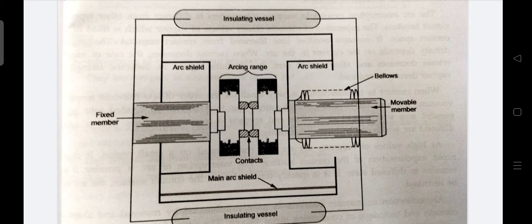For example, when contacts of a breaker are opened in vacuum, the interruption occurs at first current zero with dielectric strength between the contacts building up at a rate thousands of times higher than obtained with other circuit breakers. The principle of vacuum circuit breakers is the production of arc in a vacuum circuit breaker and its extinction can be explained as when the contacts of the circuit breaker are opened in vacuum, an arc is produced between the contacts by the ionization of metal vapors of contacts.